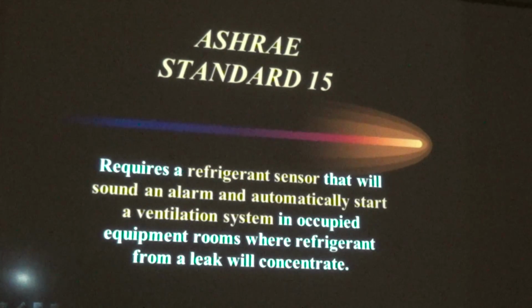Another standard, this one's ASHRAE standard 15, and it's a mechanical room, and it requires that the owners of the building must put a sensor up there that will sound an alarm if the refrigerant escapes and leaks into the area, a confined space.